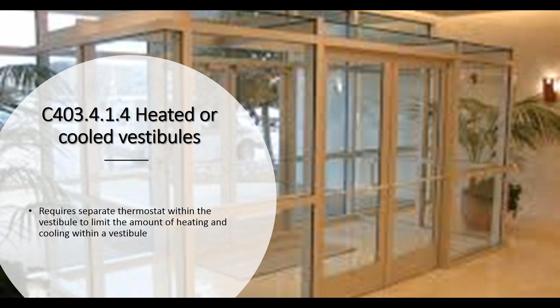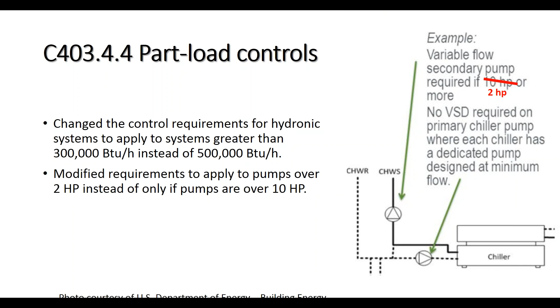Part load control, so for those designs that call out hydronic system, the code used to have requirements for part load controls that only kicked in if you had a system over 500,000 BTU. Now they kick in if you have a system over 300,000 BTU. There were requirements to automatically vary the fluid flow on hydronic systems if you had a motor capacity over 10 horsepower. Now it's if it's over 2 horsepower. So there were definitely some efficiencies changed there.